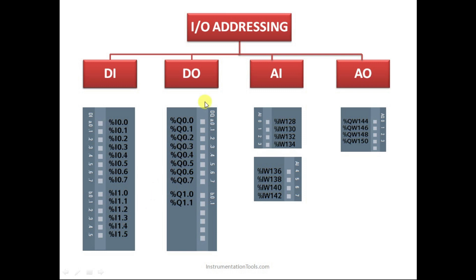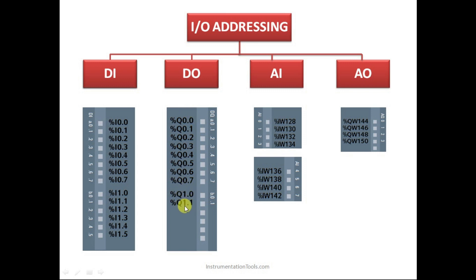For output addressing in Siemens PLCs, output is not represented by 'O' — instead we use 'Q'. The format is Q0.0, Q0.1, Q0.2, and so on. Again, from 0 to 7 the 8 bits complete one byte, after which the byte number updates. This is the output addressing format used in Siemens PLCs.